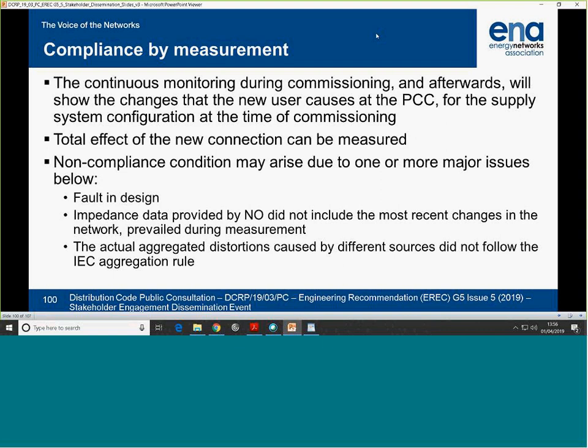All the connections we've assessed under the existing stage 3 assessment. What is the limit? Nearly always, the customer comes back and says, we comply with your limit at this given harmonic. And we have to be flexible and look at that, and see if there are more limits, or look into the impedance data. And if the impedance data is actually related to that harmonic, they are having a problem.